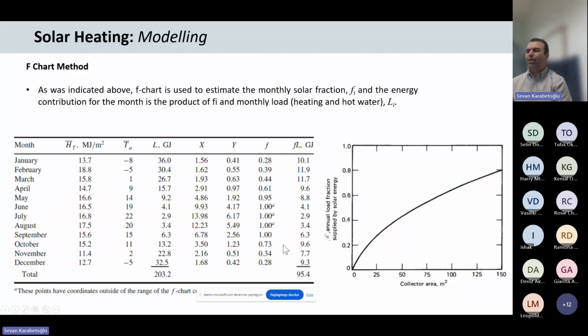So it is related to the collector area. By choosing the collector area, you can define the solar ratio. In that case, if you use 75 square meters of collector area, then annually half of your demand will be supplied by solar energy. That's how it works.